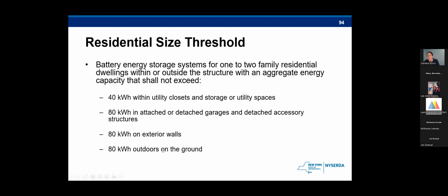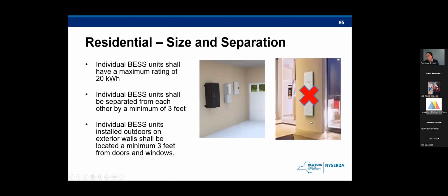But if you have the system in an attached or detached garage or accessory structure, on the exterior walls of your house, or outdoors on the ground, you can have a system that's up to 80 kilowatt hours. And if you go over that size threshold, there are more in-depth requirements that these systems need to meet, even if they are installed on residential property. So here, individual units have a maximum rating of 20 kilowatt hours, and individual units shall be separated from each other by a minimum of 3 feet. Individual units installed outdoors on exterior walls shall be located at least 3 feet from doors and windows. An average residential unit is usually around 12 to 16 kilowatt hours.